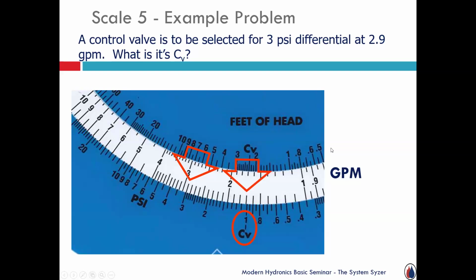So right here, I have a CV. When I look up the specs on that Honeywell valve or that whoever, Johnson, Siemens, if I get a valve that has a CV of 1.7, and I have the fitter put it into that system with that chilled water coil, that has a flow rate of 2.9 because the balancing valve guy tested it and knows it's 2.9, I'm going to have a pressure drop of about 3 pounds across that valve. I'm going to have real good control valve authority. So again, a little bit in the weeds, but it's just simply scale 5. It's that relationship of flow and head. And it kind of works. If you get that, that's big throughout your career as far as in hydronics and designing and selecting.